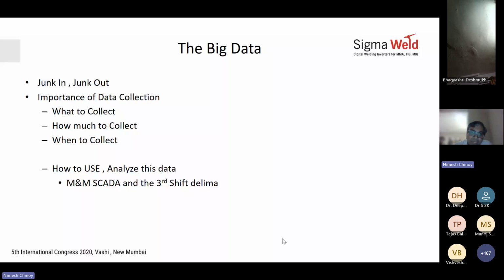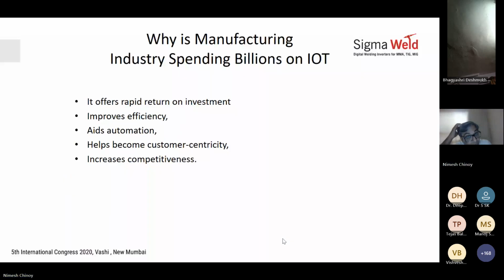With the help of SCADA and the right data collected, which clearly identified the error, they realized the only thing needed was to check whether the operator was loading the billets or not. After that, breakdown time was no more than 1-2%. So if you collect and analyze data in the right way, it becomes far more useful for the purpose you intend.